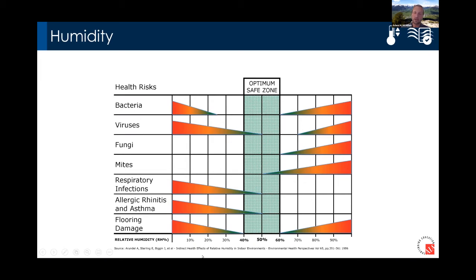And certainly in the Colorado climate, you're probably seeing a lot of indoor environments that without any humidification added are in this 10 to 20% range. So certainly on the lower end of the recommendation here. So in that case, you would need to add humidity if this is a strategy you wanted to use.